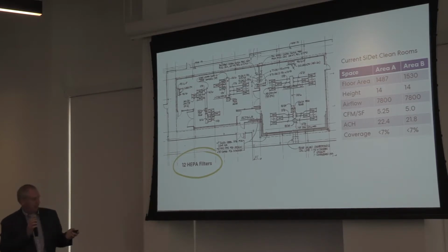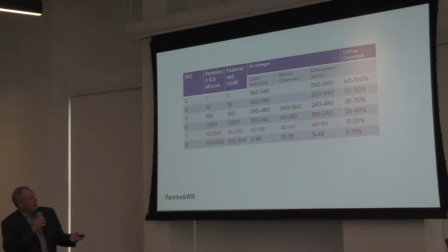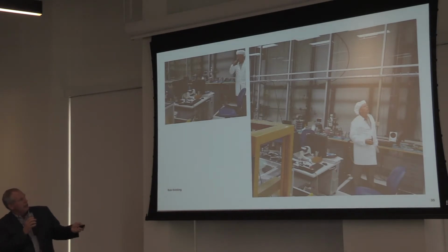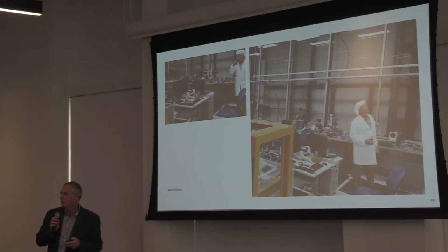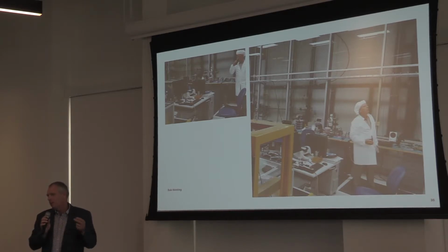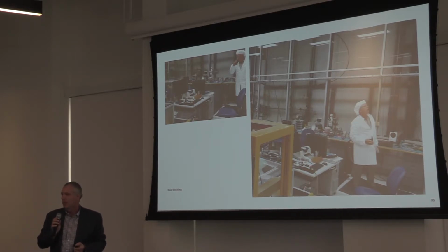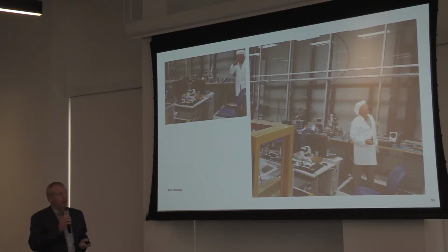One of the issues here is that this is a very tall space, much taller than any of the people doing things and generating particles. The reason for that is they move big stuff around; our new clean room actually has traveling cranes in it. So you can probably expect that the volume above the 8-foot level isn't contributing to the particulates in the room. Do you include that in your volume calculation or not? It's another one of these judgment calls.